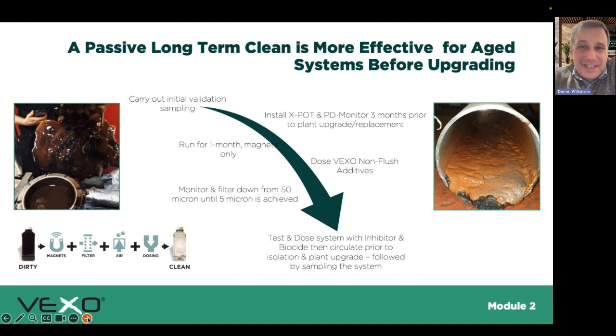For older systems, a passive long-term clean is more effective before you upgrade. If your client wants a plant room refurbishment and you need to connect to an existing circuit, the best time to make a difference is 3 to 6 months beforehand. I've seen systems take a year to get clean using this non-invasive approach, basically using additives to gently remove deposits.